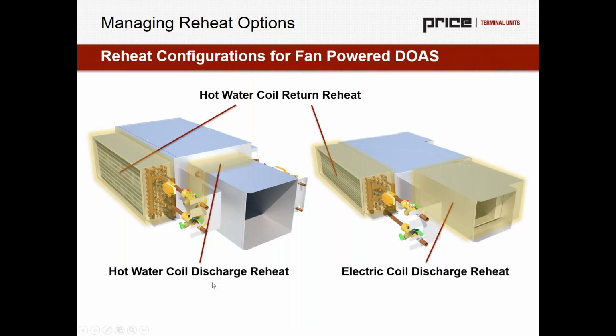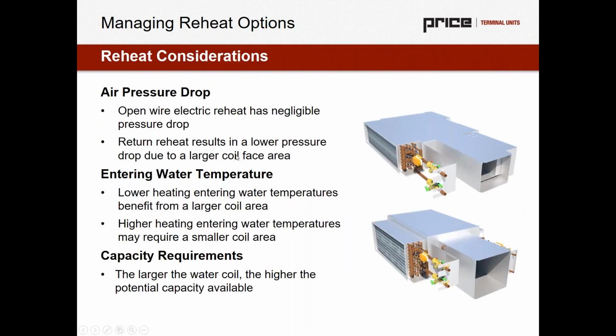And all of this is really important when we look at hybrid system design, because I would tend to suggest that this kind of equipment is really best serving exterior zones with high heating loads or maybe variable loads, high cooling loads in the summer as well. So when we're considering these different reheat options on our fan-powered units, I think the biggest thing for the Seattle market, which tends to be, in my experience, a hydronic reheat market on this kind of equipment, and it also tends to be a very, very low heating entering water temperature market, we would really want to evaluate is the return coil optimal for us with our low entering water temperatures, which I would tend to say it is.